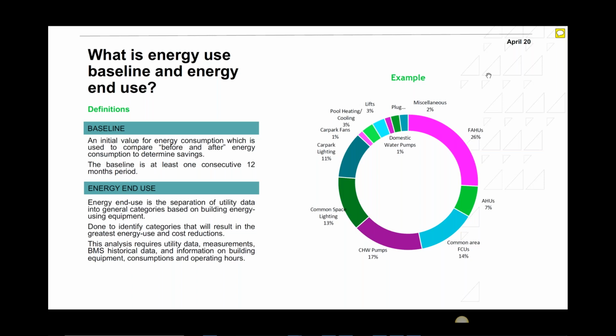I would really not look into the lifts, it's not going to save much. Even if I save 50% of the lift's energy consumption, it's not going to end up with a lot of savings. So I would focus on the lighting, the chilled water pumps, and the ventilation as well.